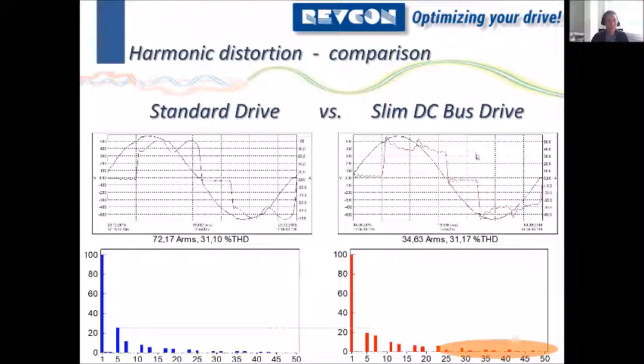So if you have a few slim DC bus drives, they can actually benefit your harmonic situation because they would eliminate others. But in the end, you will have to evaluate it if you only have slim DC bus drives. There are two dangerous things. A simple harmonic filter would not be able to handle the higher order harmonics. And also these harmonics cause a lot more harm than the lower order harmonics, so the fifth and seventh.